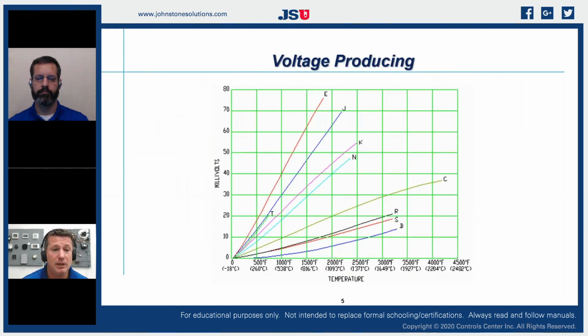It's very predictable. And that Seebeck effect, we could actually calculate how much voltage was being produced by a thermocouple to know how many of them we needed to put together to make our thermopile. So depending on the type of thermocouple, we could look at specific voltages that it would produce at desired temperatures. So we know that most of our combustion process for natural gas, even in LP, we're somewhere in that 3,300, 3,500, 3,600 degree Fahrenheit range for our combustion process. So we're going to work with that C-type thermocouple. A lot of the other thermocouples won't go that high.